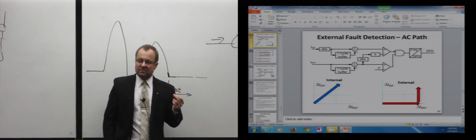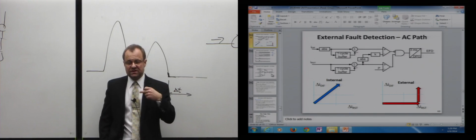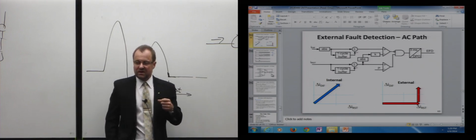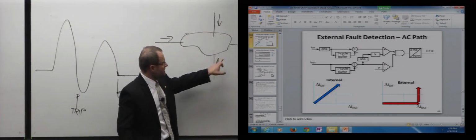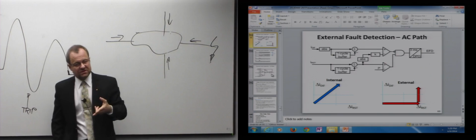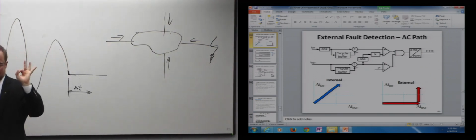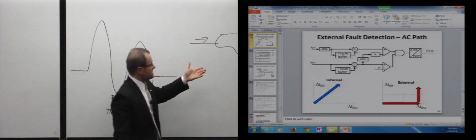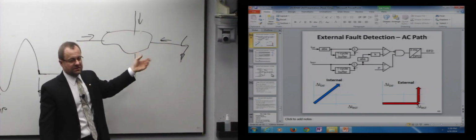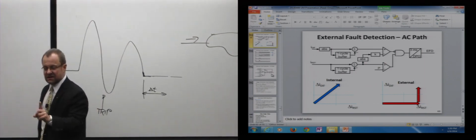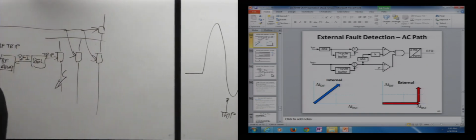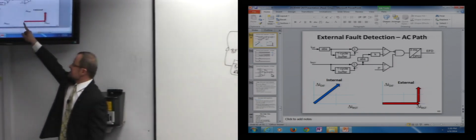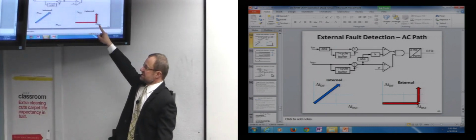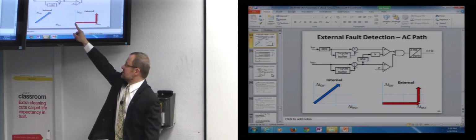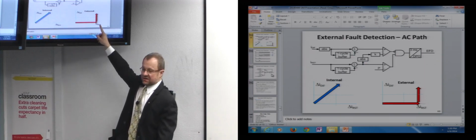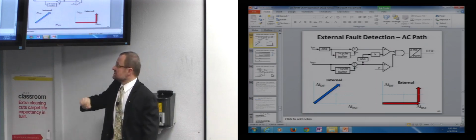So saturation happens after a few milliseconds, and it starts producing a false differential signal. But before it happens, the sum of this current, this current, this current, and this current, known as the differential signal, is going to be 0. Right? Because the fault is outside, what's in, it's out, the differential current is 0. CTs are not lying to me yet. They tell the truth for the first 3 milliseconds. So the differential current stays low. So I see this move. Oh, there is a fault, and CTs start to saturate. So there is a fault. If CTs don't saturate, I stay here. And if CTs start to saturate, I see this distinctive pattern.